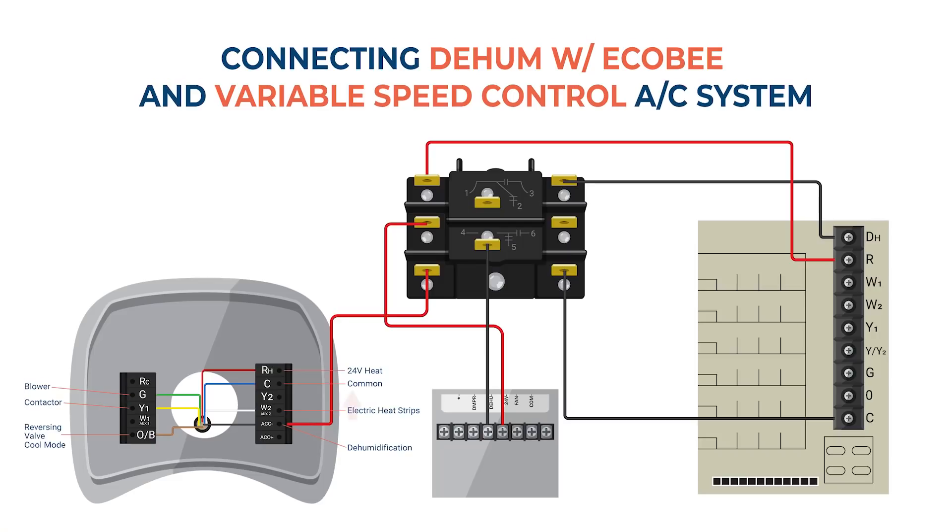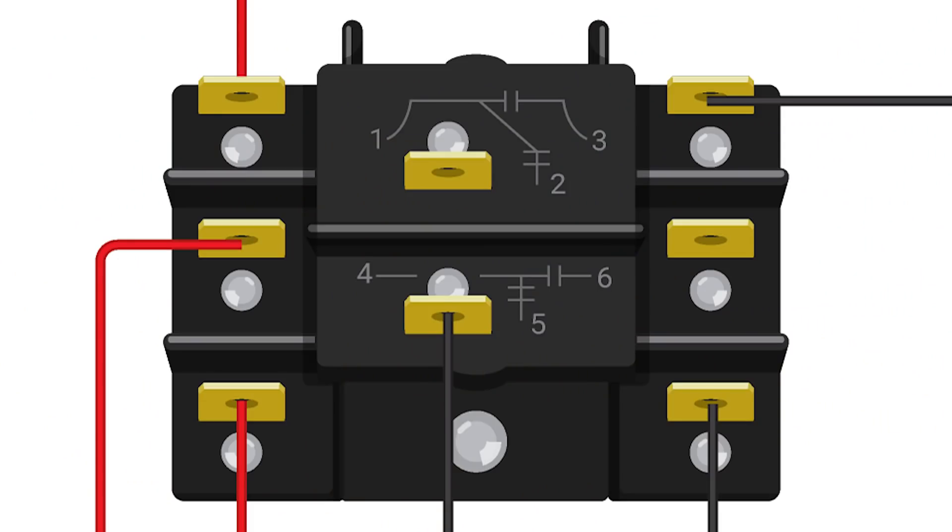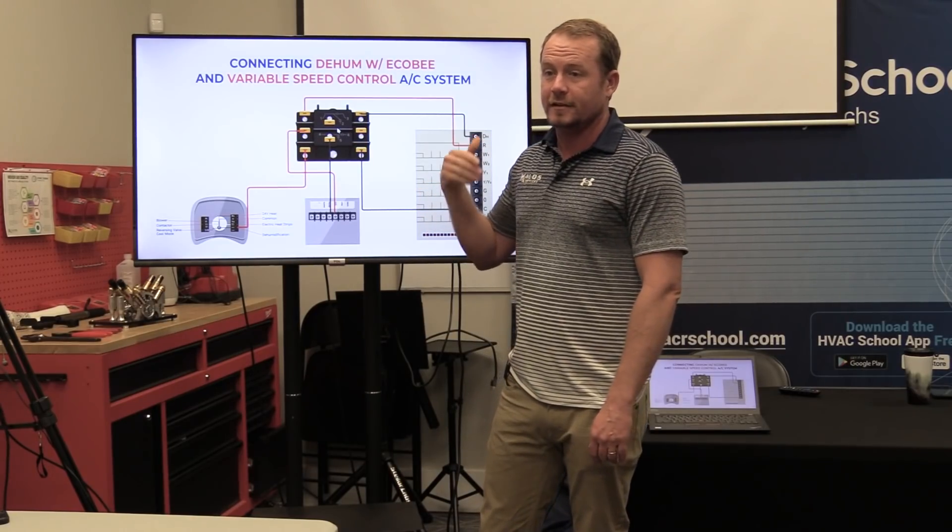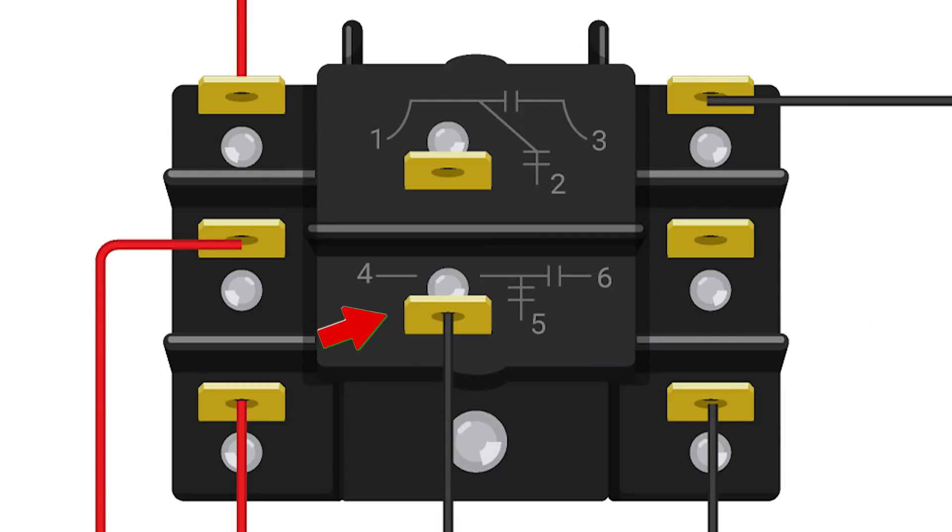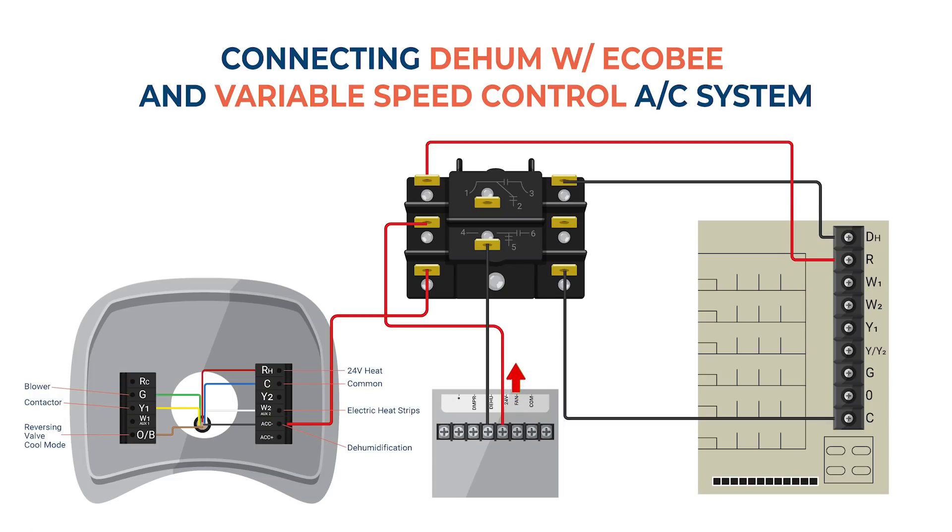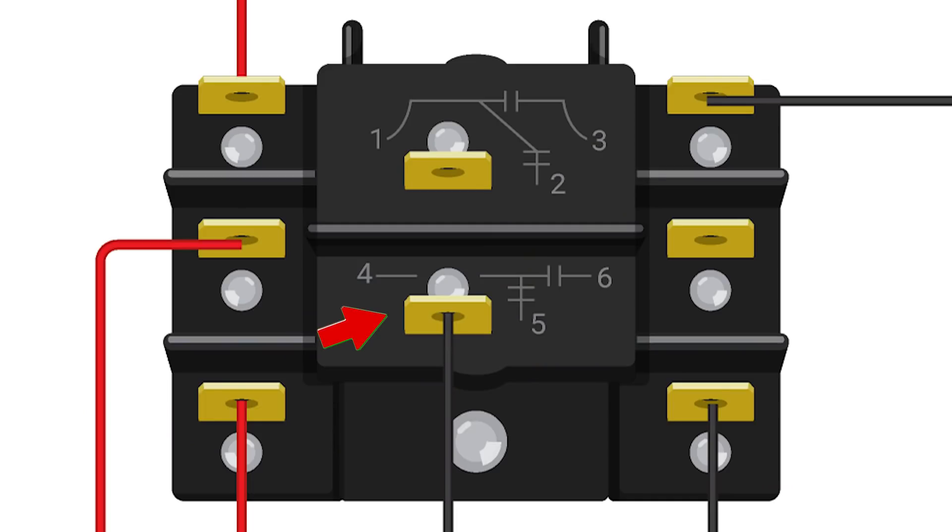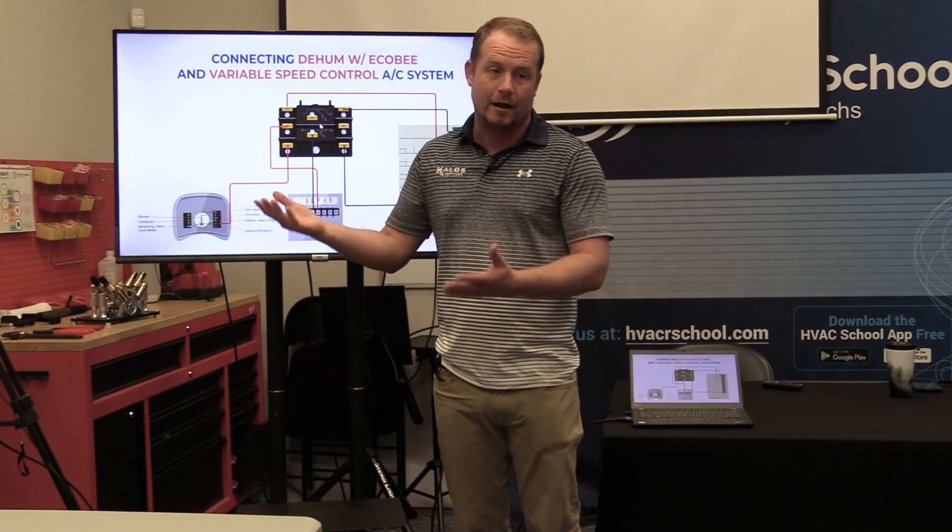So the way this is wired, when this thermostat says we do not want to dehumidify, now it energizes like it normally would. It energizes this coil, this 24 volt coil, it pulls in the contacts. These go closed because they're normally open, it energizes, these go closed, you energize DH, which keeps it in full speed. You energize for full speed. And now these, because these were normally closed - this is 24 volts from the dehumidifier transformer back to dehumidify call on the dehumidifier. Then these that were normally closed now go open in order to not run the dehumidifier.